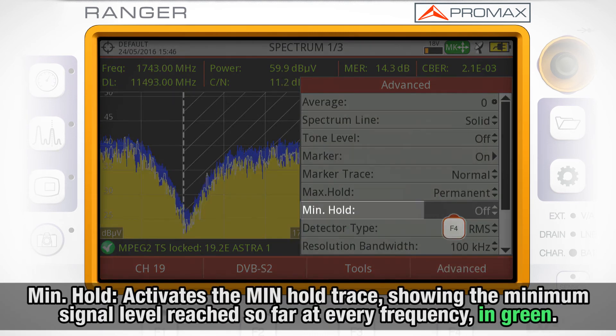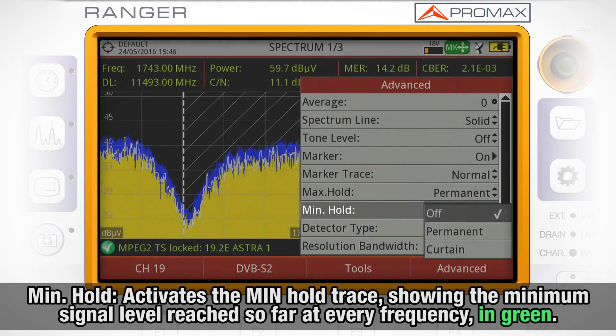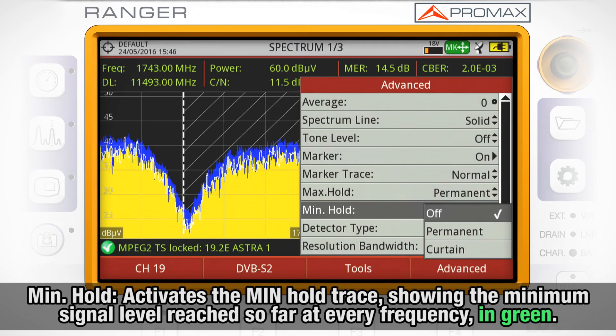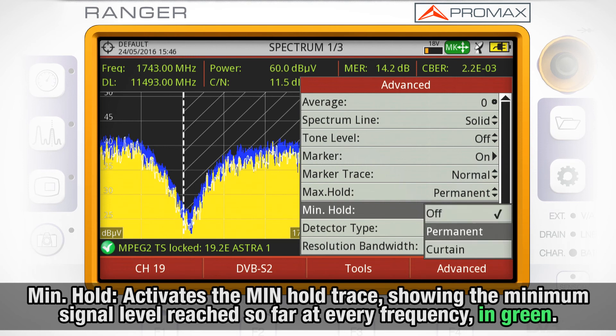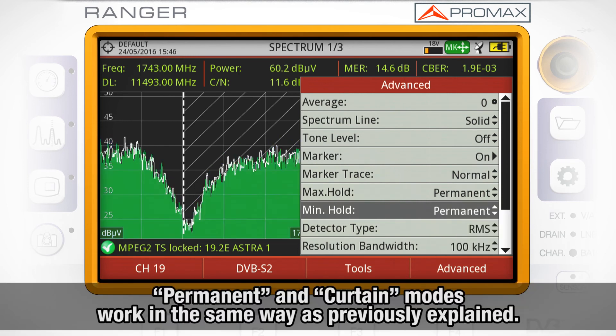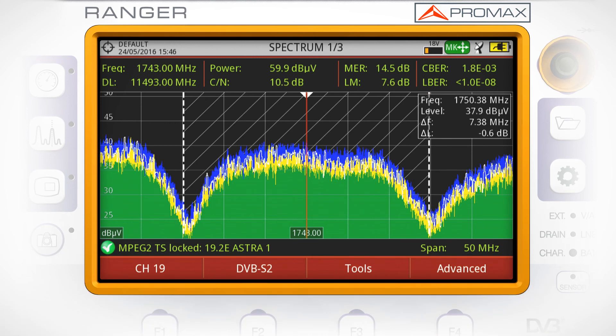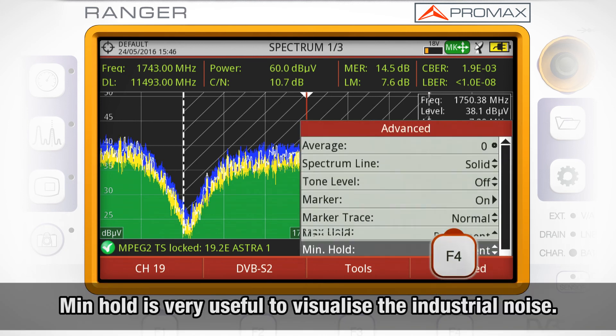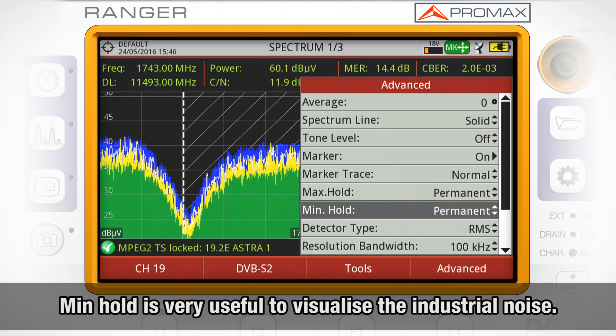Min hold will activate the min hold trace, showing the minimum signal level reached so far at every frequency, in green. Permanent and Curtain modes work in the same way as previously explained. Min hold is very useful to visualize the industrial noise.